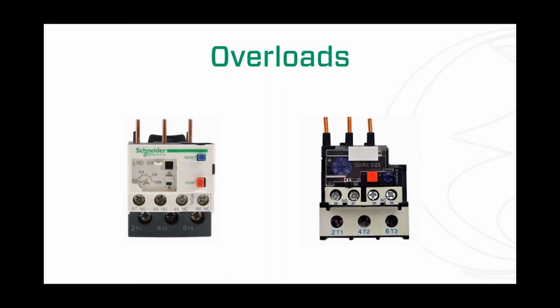One thing I preach a lot is that heat is the killer of the electric motor. These overloads aren't there to be a nuisance, they're there to protect your pump and your system. When they trip out, they're doing it for a reason. We want to keep heat from building up in the motor, because amps equate to heat, and heat is the killer of the electric motor. So we want to shut the pump off as soon as we know there's a problem.